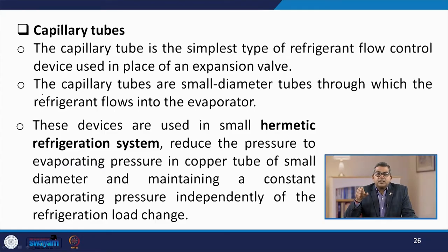The capillary tube is the simplest type of refrigerant flow control device, used in place of an expansion valve. Capillary tubes are small diameter tubes through which the refrigerant flows into the evaporator. These devices are used in small hermetic refrigeration systems to reduce the pressure to evaporating pressure in a copper tube of small diameter, maintaining a constant evaporating pressure independently of refrigeration load changes.